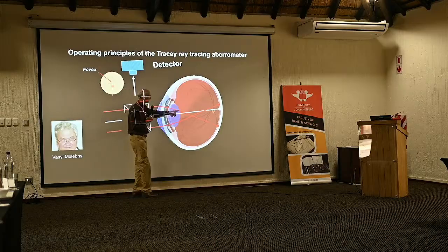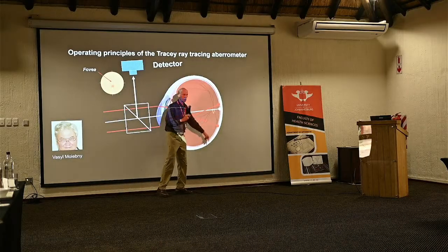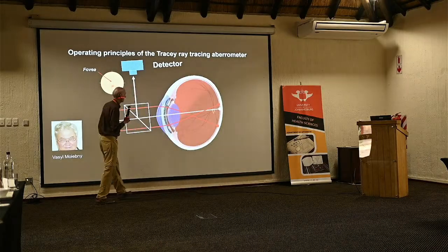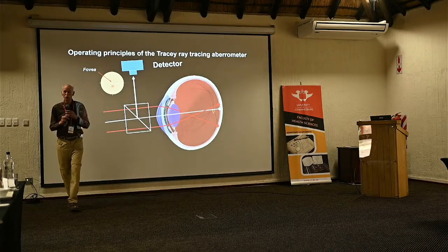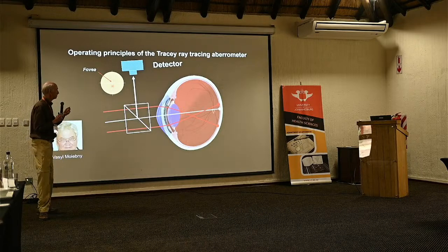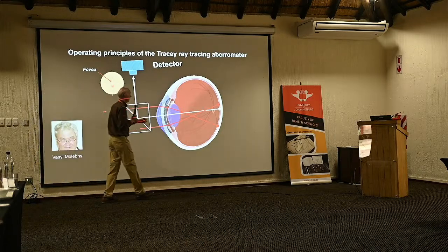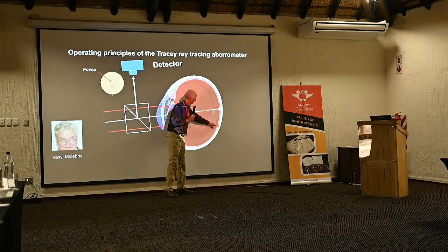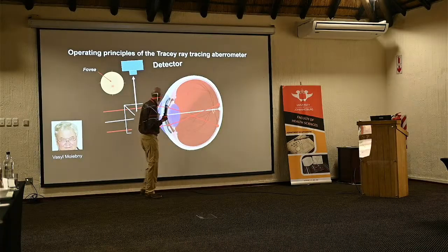And then the laser beam is going to go in, and it's going to land someplace because it's aberrated, right? And he wants to know where that ended up. But it's not a subjective thing where you've got a person saying, "Oh, I see two points coinciding or coming together to a single point." This is an objective instrument. And so the objective instrument has to measure where that spot is compared to the reference. So what does he do?